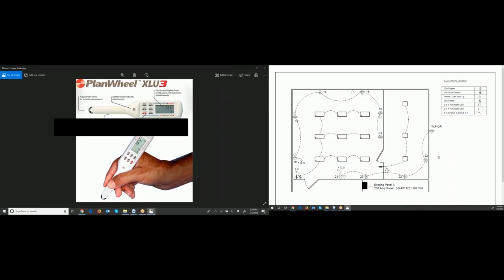That's what you use for conduit takeoff. These blueprints are a single dimension — not three-dimensional. The conduit has to come up out of the switch, go up the wall, then across and over to the light fixtures, daisy-chaining fixture to fixture. Same with receptacles — if they don't stub down the wall, they have to go up, over, and down with conduit.